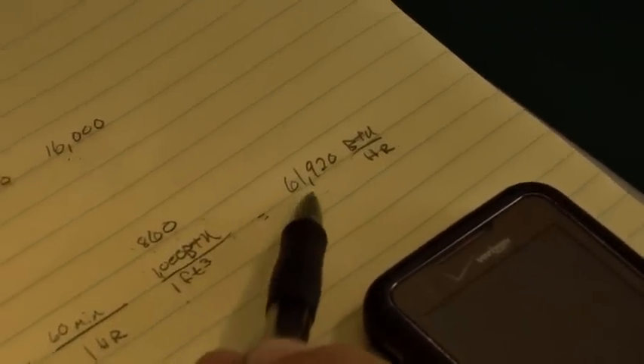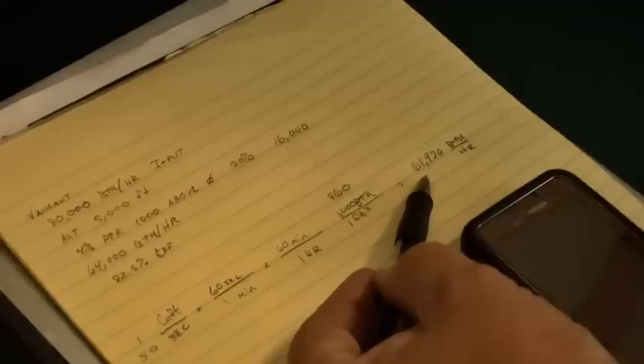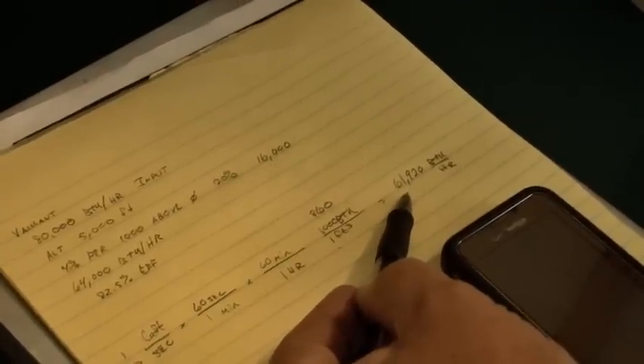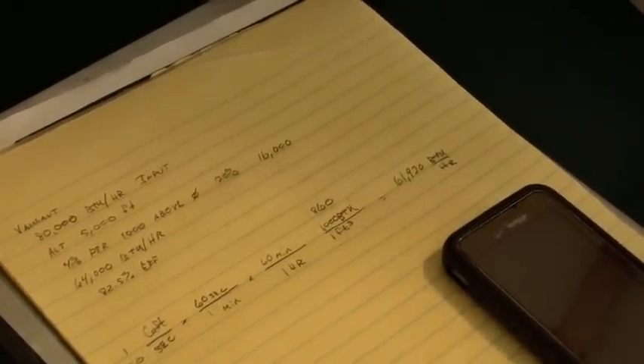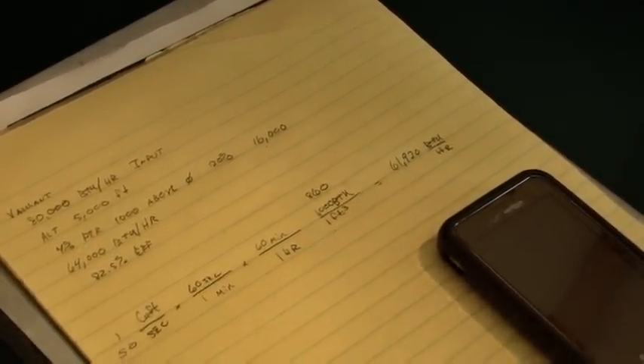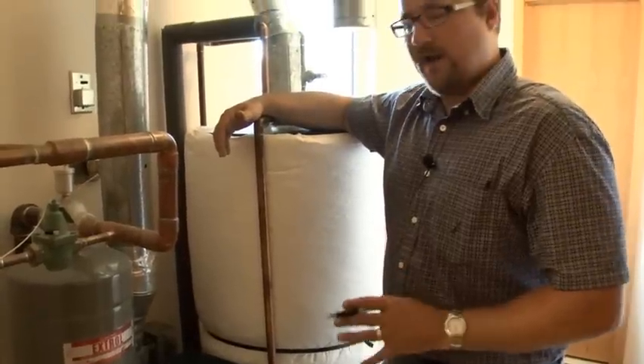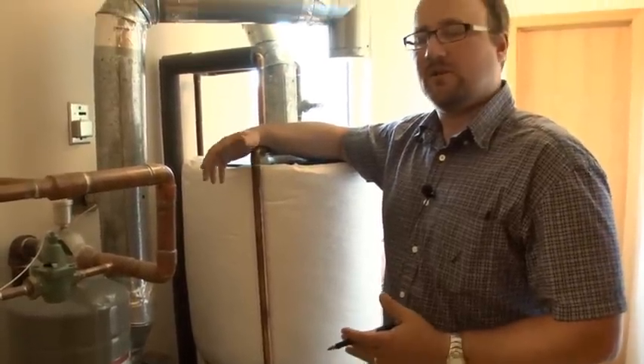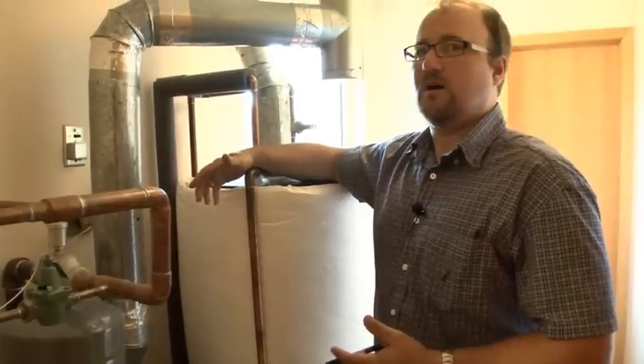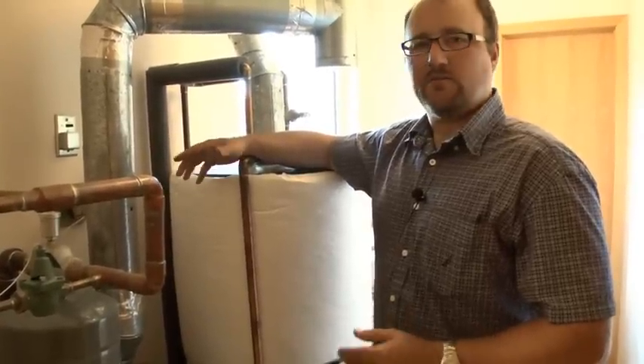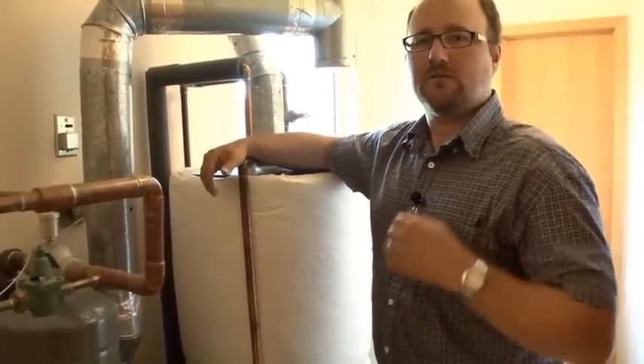Based on our math for our altitude, we should be right around 64,000 BTUs per hour of input. We calculated 62,000 BTUs. We're a little under, which is great. So we're putting in the right amount of fuel. We're a little bit under, but that's okay. Better than too much. Indications so far tell me we're going to have a pretty good burn on this appliance.